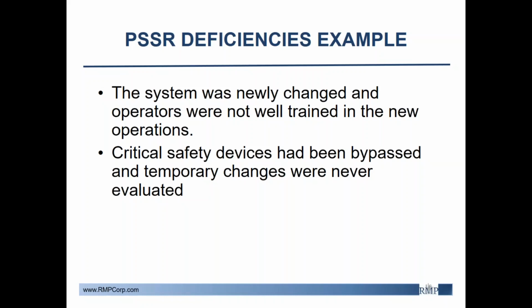So if they had done the PSSR form, they would have caught that operators weren't trained. They didn't quite understand how to use the process. They would have evaluated in a safety review if it was okay to start up with the critical safety devices bypassed, and if they had figured out a procedure to do it safely so that this terrible accident wouldn't have occurred, right? So it's important to remember that there are ramifications for not doing these things, and that's why they exist.